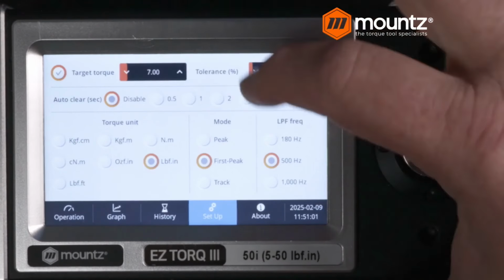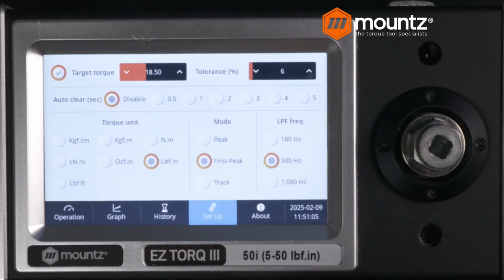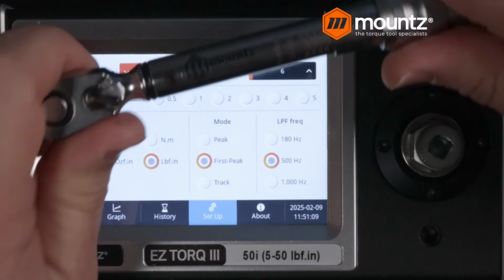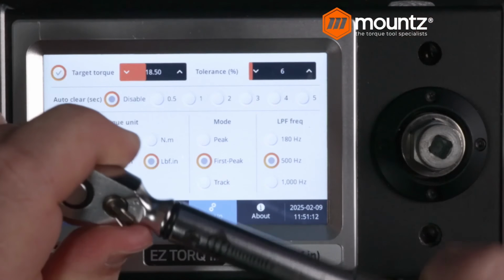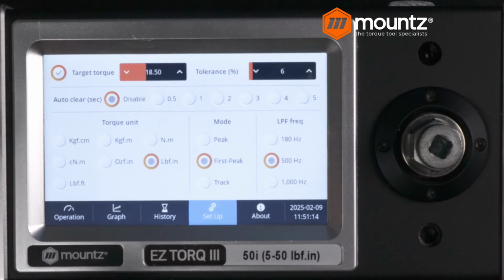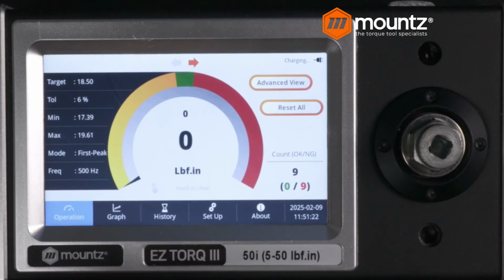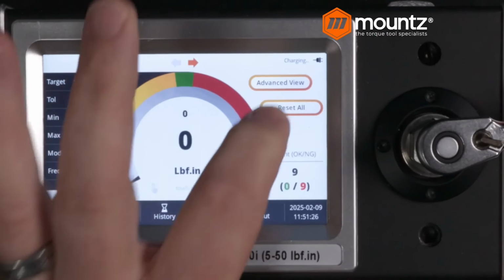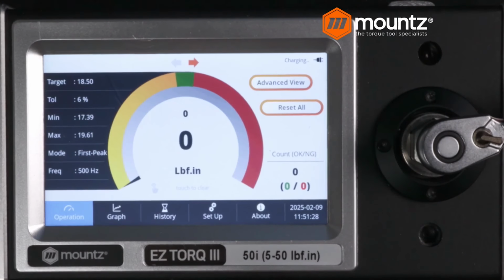Now, because of the makeup of a click wrench, it's a very operator dependent type of tool. And so if the operator keeps pulling on it after the click, we are adding additional torque to that. And so if we were using it in a peak mode, we may see very erratic readings as it relates to that. So let's go ahead and we'll reset our values.